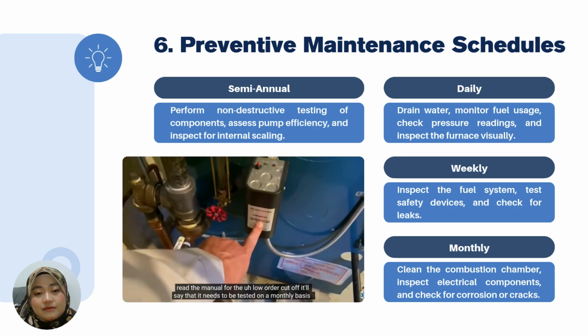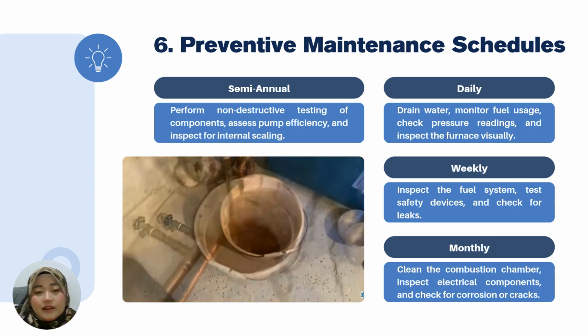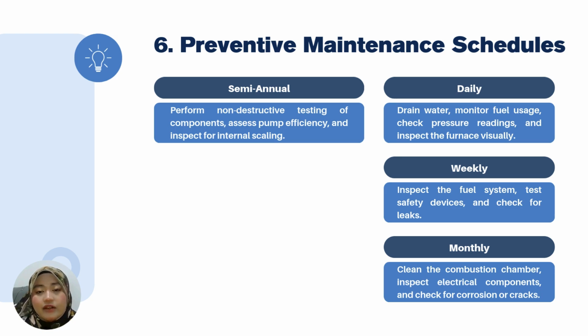However, if you read the manual for the low water cutoff, it'll say that it needs to be tested on a monthly basis. See, we have the monthly draining of boiler water. But in this presentation, we can have four different types of maintenance schedules. It revolves around daily, weekly, monthly, and lastly semi-annual. Daily revolves around daily draining water, monitoring fuel usage, checking pressure readings, and inspecting the furnace visually. Whereas weekly involves inspecting the fuel system, testing safety devices, and checking for leaks. While monthly revolves around cleaning the combustion chamber, inspecting electrical components, and checking for corrosion or cracks. Lastly, the semi-annual performs non-destructive testing of components, assesses pump efficiency, and also inspects for internal scaling.